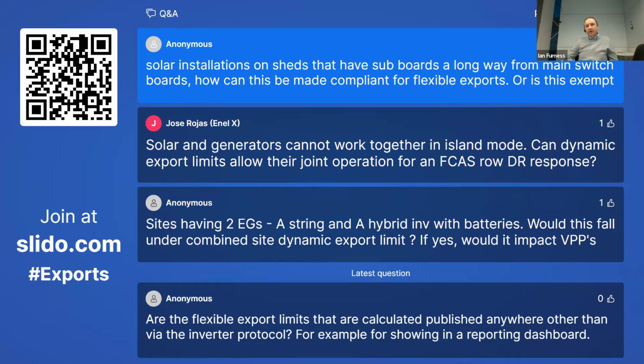I think one of the important things to point out here is that it's been fairly straightforward to achieve export limitation by limiting the inverter capacity. If you've got a 5 kilowatt inverter, you don't need to worry about measuring the exports if you're on a 5 kilowatt export limit. When that goes down to 1.5 kilowatts, it's a lot harder to achieve using that solution. So in a lot of cases now, there'll need to be some way of measuring the exports, or you're going to end up with a very small system, 1.5 kilowatts. So. Thank you.